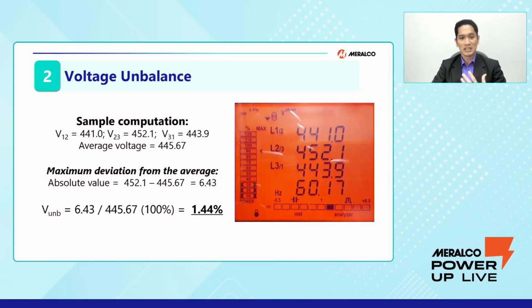So in computing the voltage unbalance, 6.43, we divide by the average of the three-phase voltages, that is 445.67 volts, and multiply by 100%, resulting in 1.44% voltage unbalance, which is way below the 2.5% allowed in the Philippine Distribution Code.